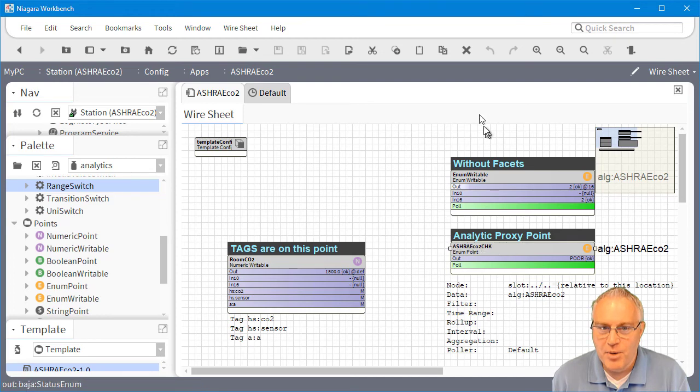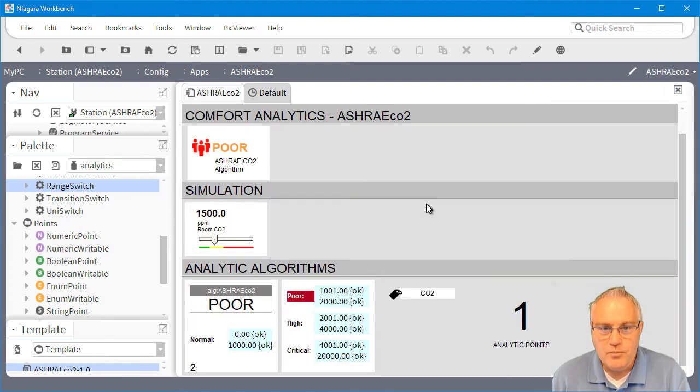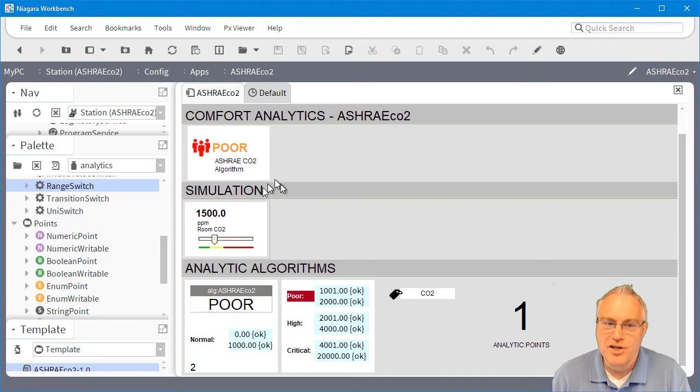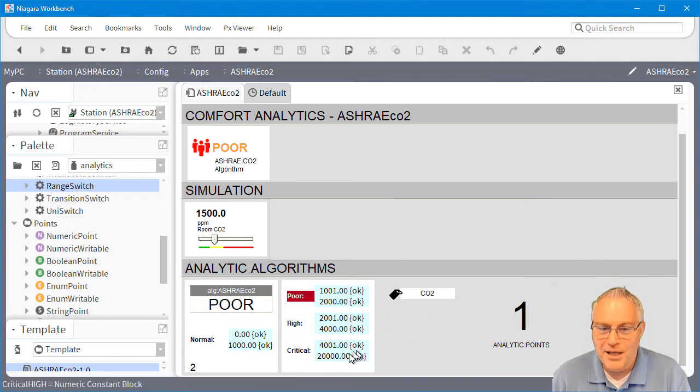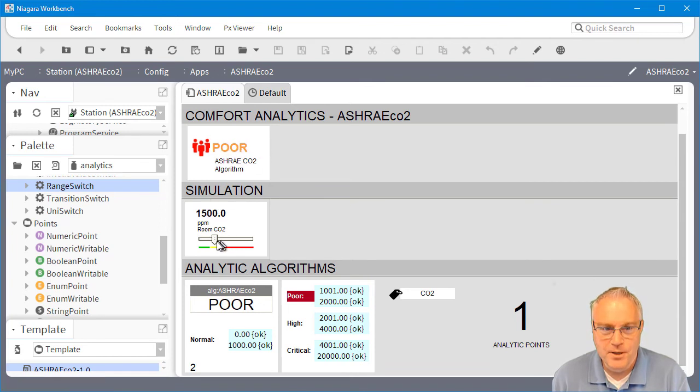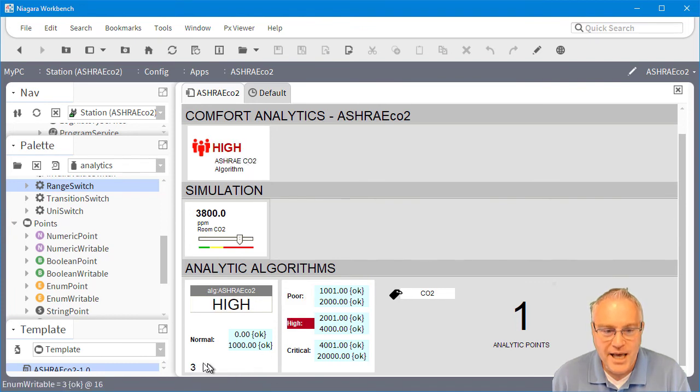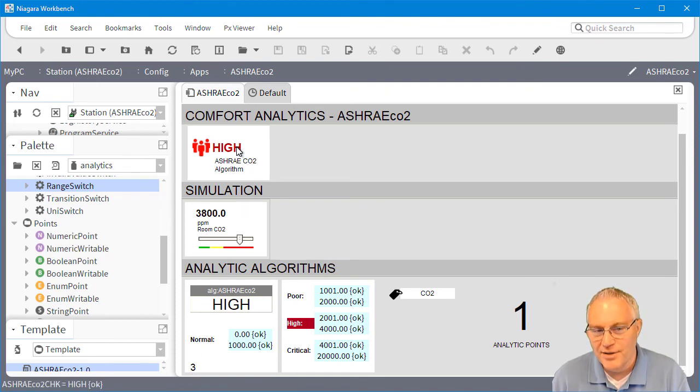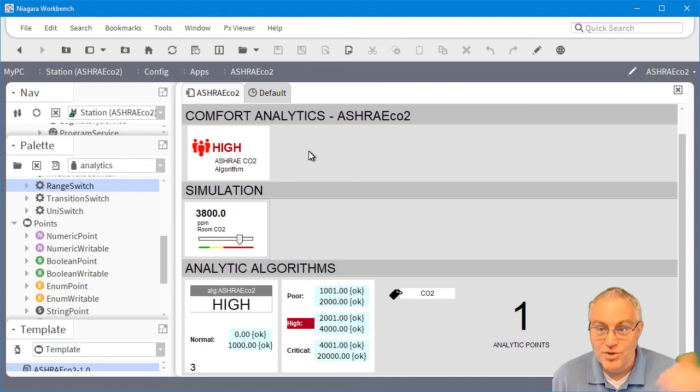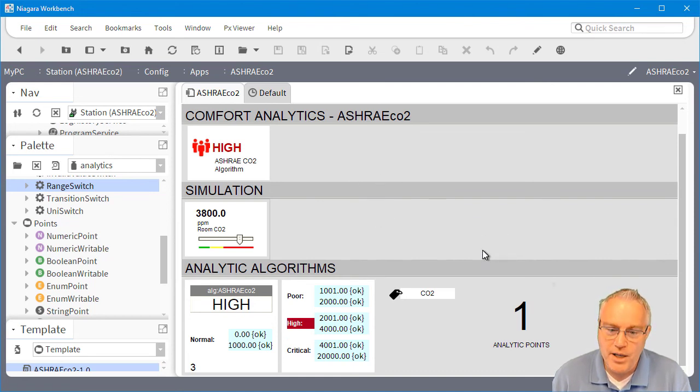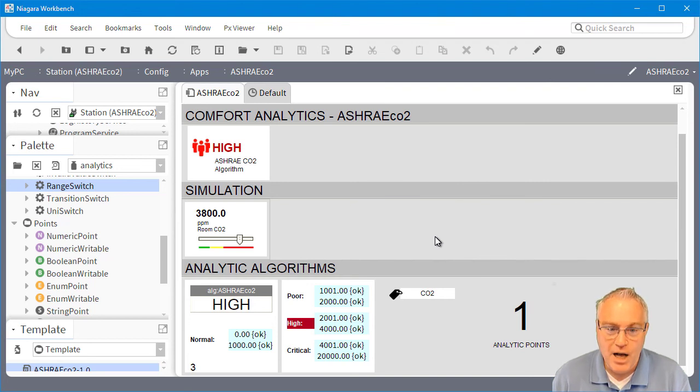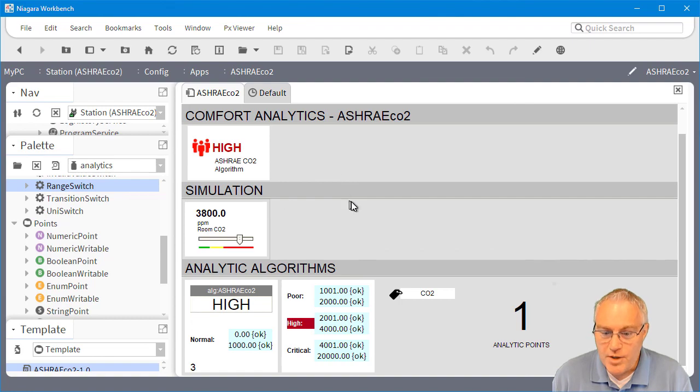Once this is all done with that equation in there, copy and paste and you're off to the races. You don't have to worry about setting those facets. You don't have to worry about coming up with what that range is. If ASHRAE would ever change that range, I would just change it in my algorithm up there. This is just visualizing what's happening inside the algorithm. You don't have to have any of that stuff. You just need this. We can make it critical, go and tell it to execute the poll down here. Why I had to do it in two places is I have that second proxy point. If I manually poll it, I have to tell both to go. If it passes through the five-minute mark, they both execute at the same time. So there is a way of looking at CO2, evaluating it with the ASHRAE standard to tell me whether it is normal, high, poor, or critical. Drop that in your station and you're up and running with that evaluation of comfort.